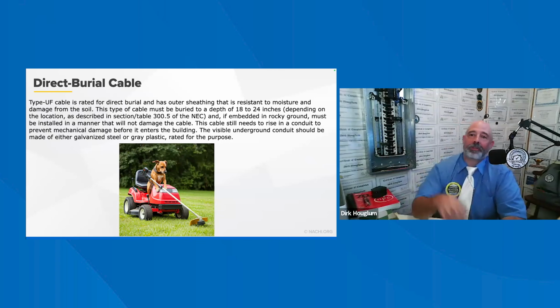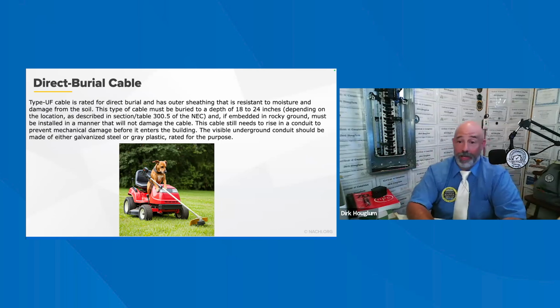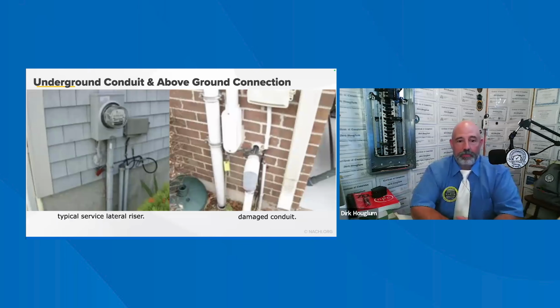Normally these service laterals are buried 18 to 24 inches underground, depending on the soil condition, sometimes with type UF cable rated for direct burial. Other times conduit is used to prevent damage, made of galvanized steel or gray pipe rated for that purpose. So when the cable leaves the ground, normally it channels up into conduit, into the meter box or conductor box. And you can actually find these wires if you have one of those electrical sniffers and you put a Romex wire on there and you can stick it in the ground and you can actually find where it is. So, little knowledge you might use, might not.